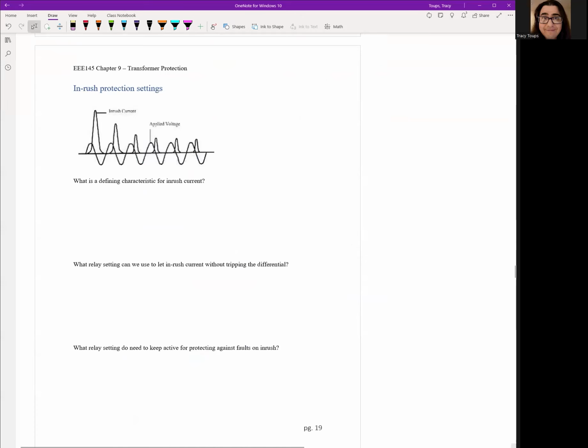So now let's talk about, well, how do we actually do that? How do we program the relay? How does the relay know what is an inrush current? So the big thing with inrush current is there's a DC offset. So if you notice, the waveform is not equal across the zero axis. So typically in an AC system, you'll have a positive half and a negative half, and they're usually equal. But notice that there's kind of like a bias to a DC component like this, right? And so this is your DC offset. So the peak is much higher, but there's no negative cycle. It's only positive cycle. Okay.